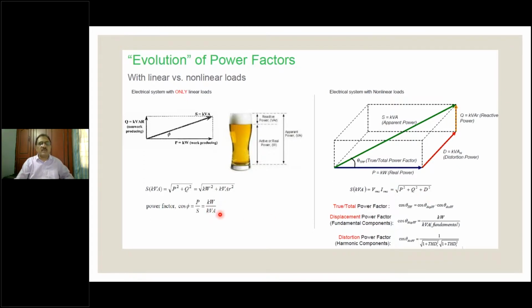Earlier, power factor was kilowatt by kVA. Now, it will be true power factor. That means you will have THD multiplied by TDD, both multiplied and shown. And that is what will be true power factor, as you can see here. Now the true power factor will be 1 divided by the square root of 1 plus THD square. Voltage and current, both get multiplied for you to arrive at the power factor, which is called the true power factor.